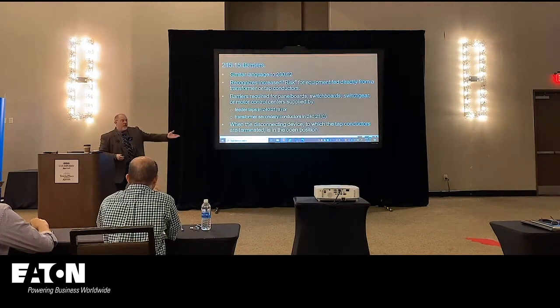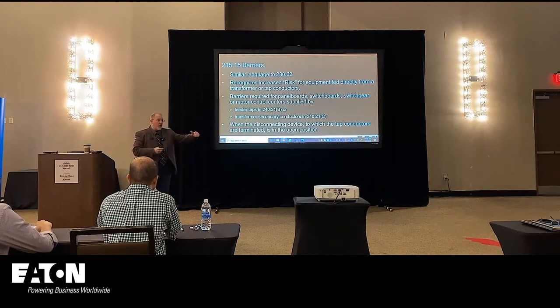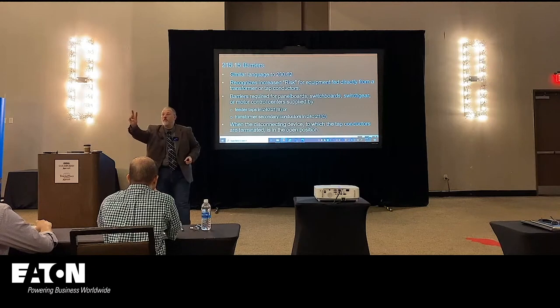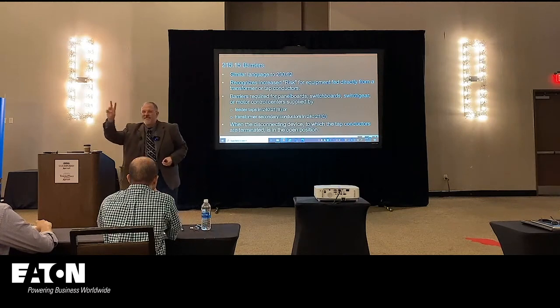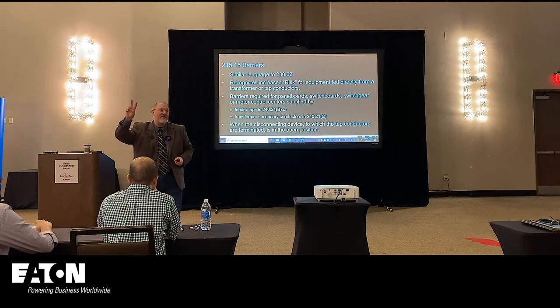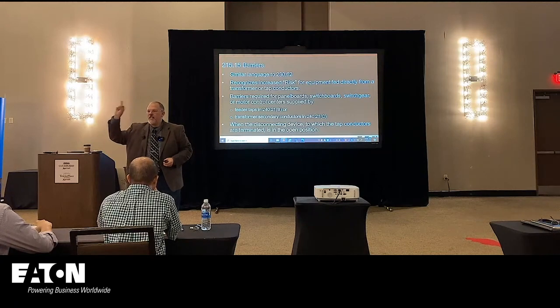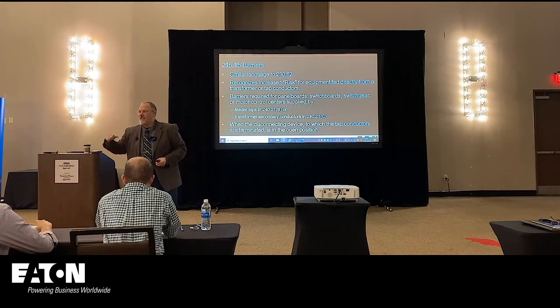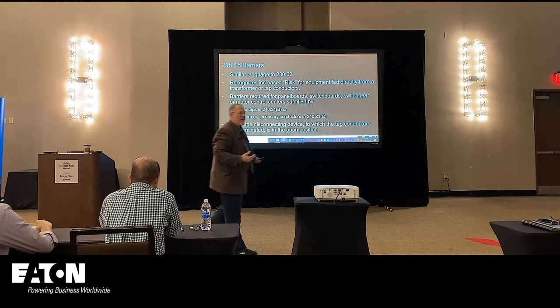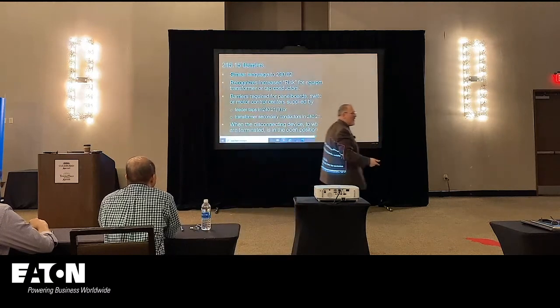The same barriers that we have on service entrance equipment, in 230, we put barriers on 230 because of why? What are the 2 elements of risk? Come on. I'll give you one: likelihood. The likelihood of an event happening. What's the other? Incident energy. Incident energy is a type of hazard. It's the severity. It's likelihood and severity, right?